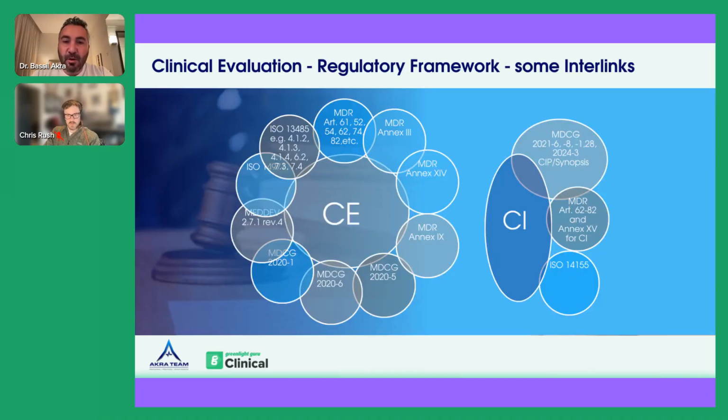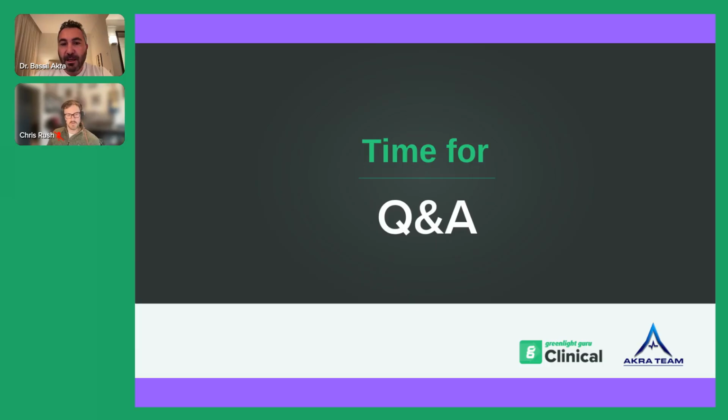So if we look at the clinical evaluation itself, it's a connection between clinical evaluation and clinical investigation. There are a lot of annexes and articles in the regulation which allow you to understand more about it. Very important as well is the ISO 14155, which gives you good principles on how and what kind of data planning would be considered to be good quality. And this kind of methodology would allow you to have a higher level of success if you build your clinical strategy for European application.